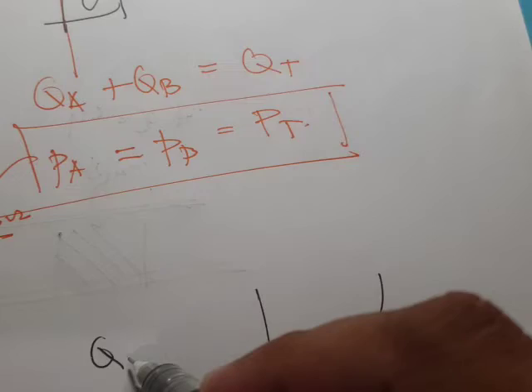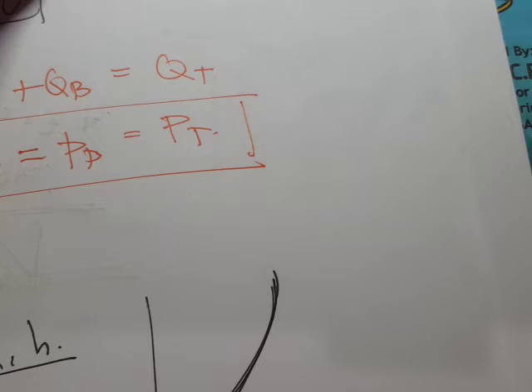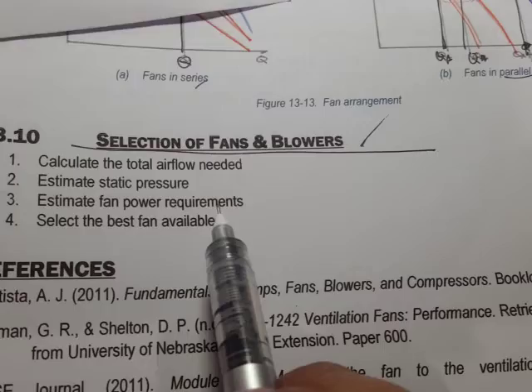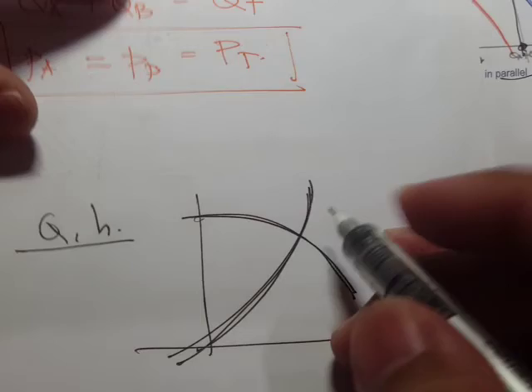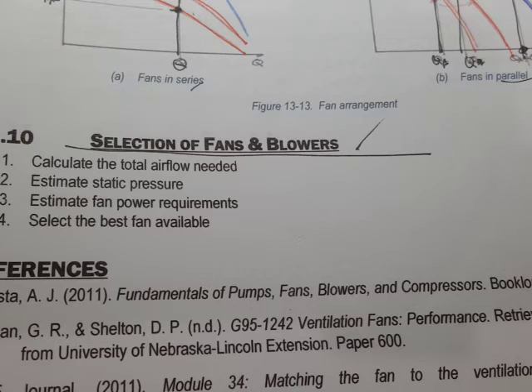For fan selection: first, compute the total required air flow rate and the required static pressure from the system resistance. Then estimate the fan power requirements. Finally, consult fan catalogs, performance curves, or performance tables to select the most appropriate fan. That concludes our topics on fans and blowers. The next topic will be pumps.